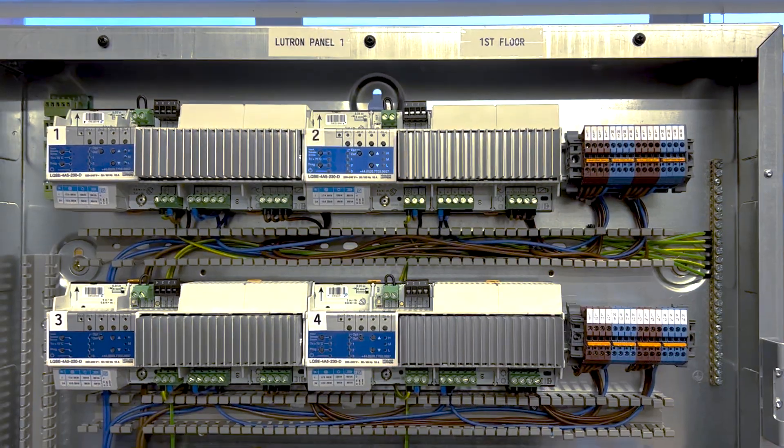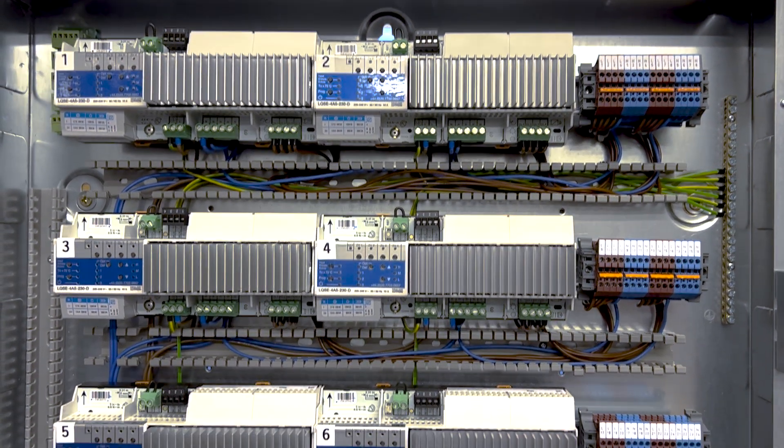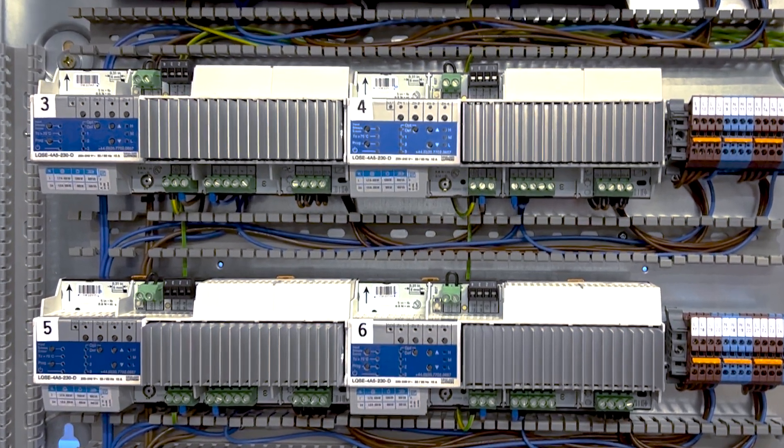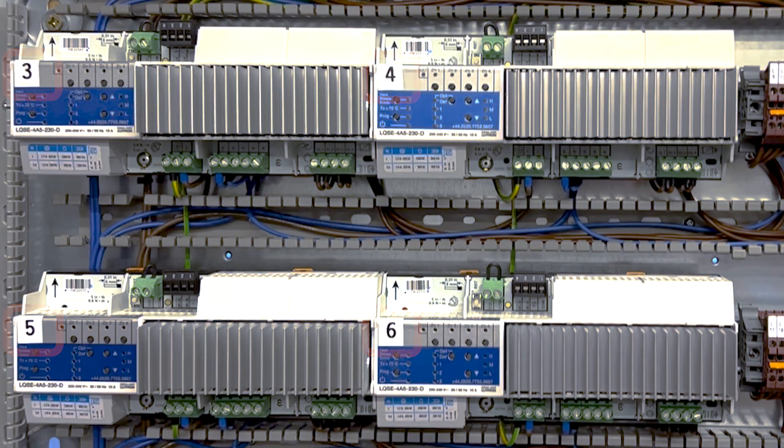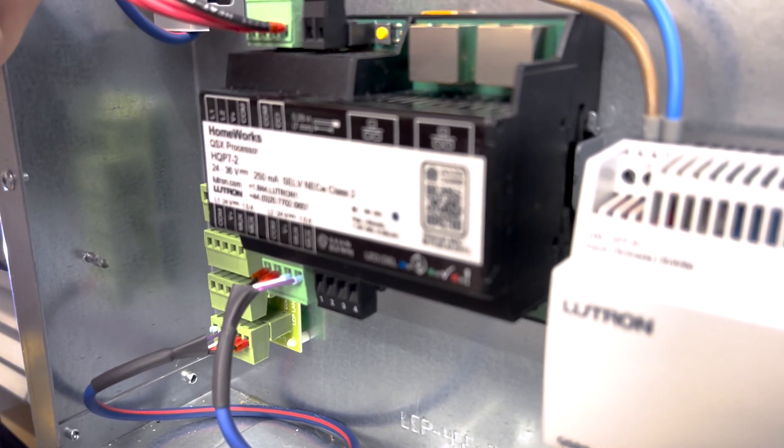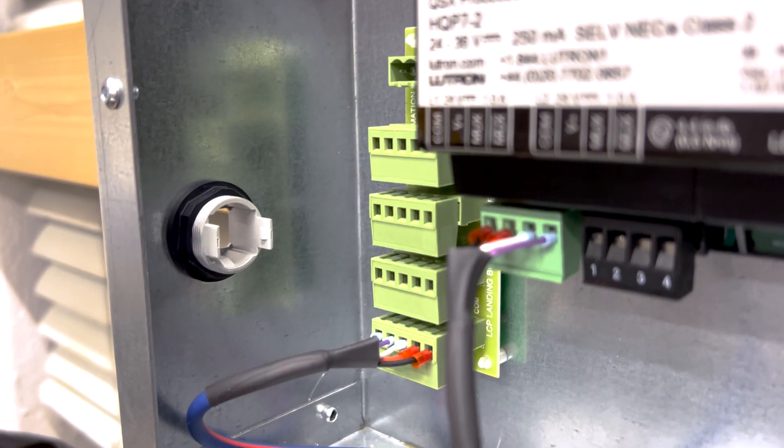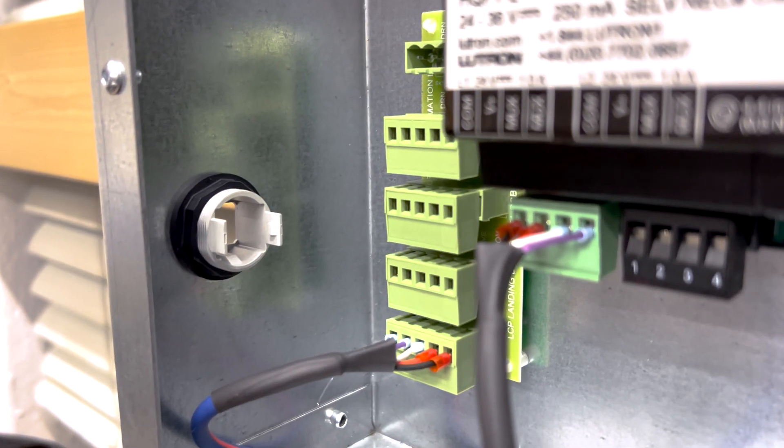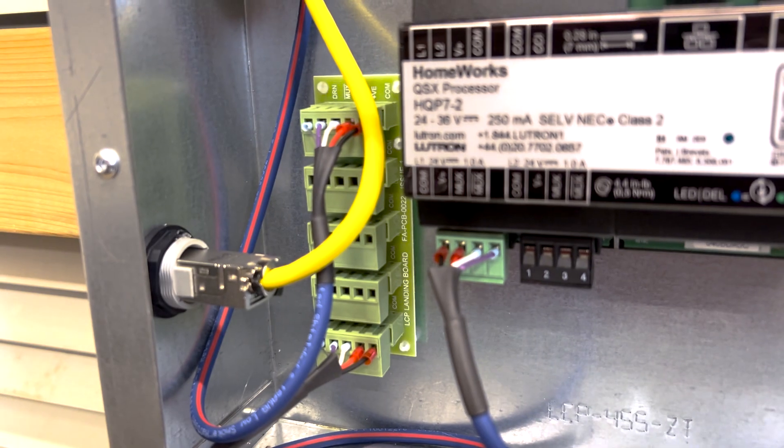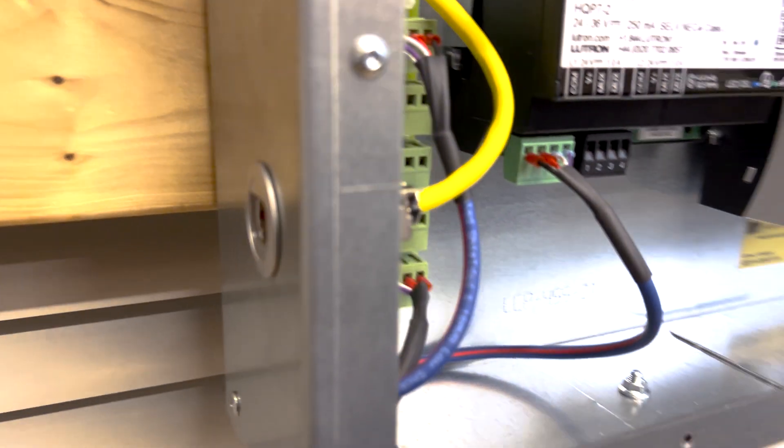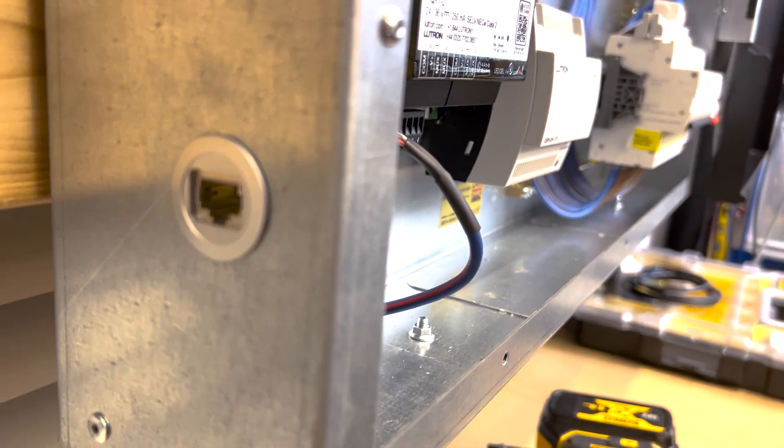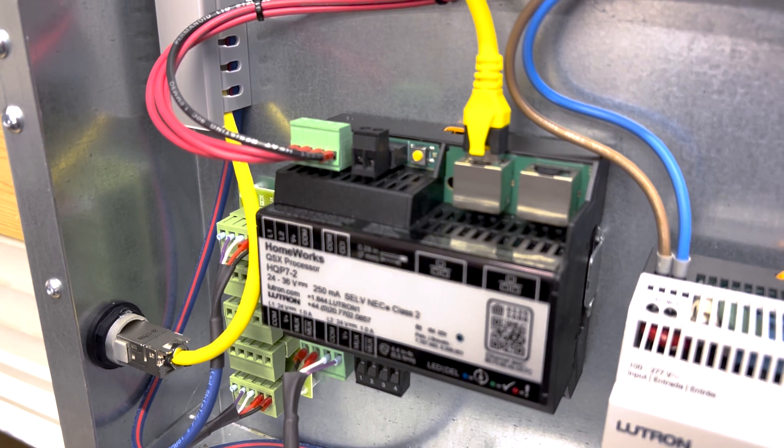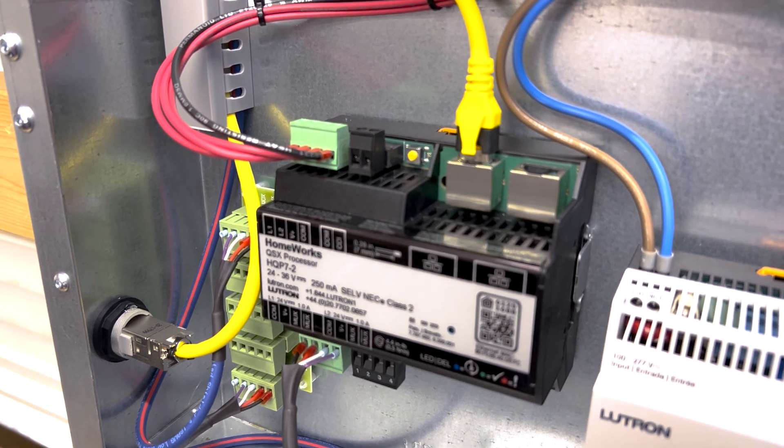I also like to label the Lutron modules, as you can see here, on a different panel I've done recently. And I like to customize it a little bit, by adding this Ethernet port here. That allows me to connect my laptop to the processor, without opening the panel, if I need a wired connection to it, and don't want to go through the house network, during the commissioning phase, or for maintenance.